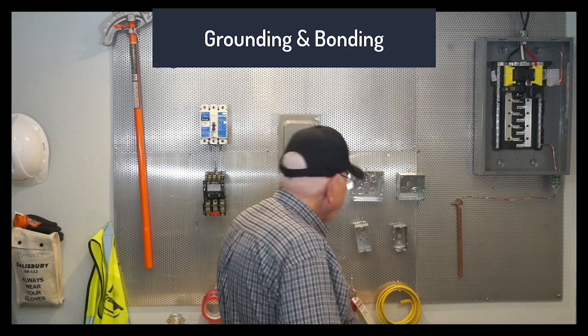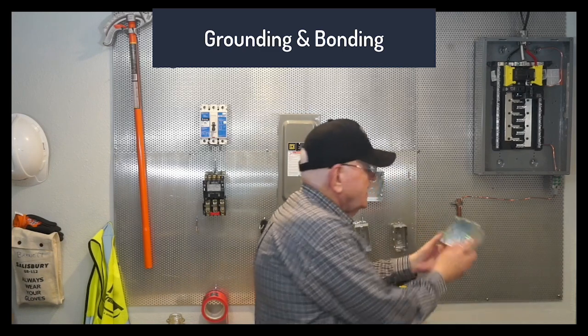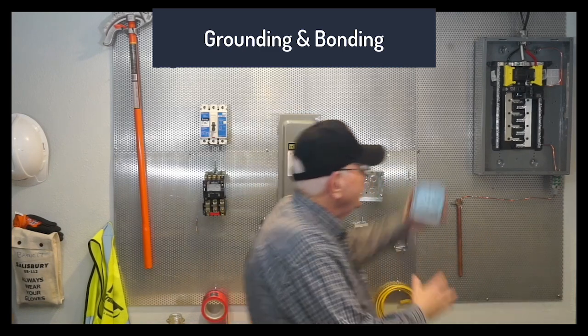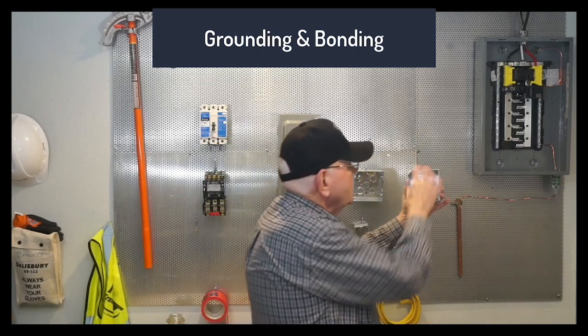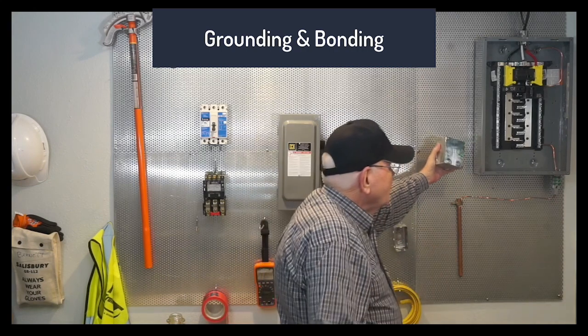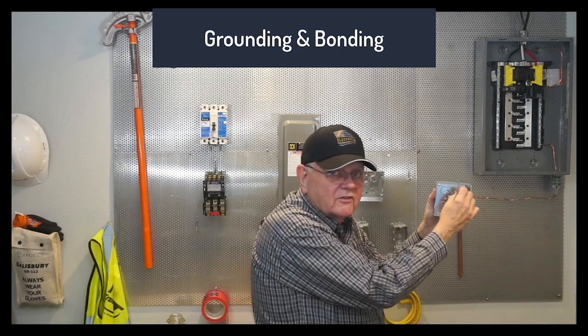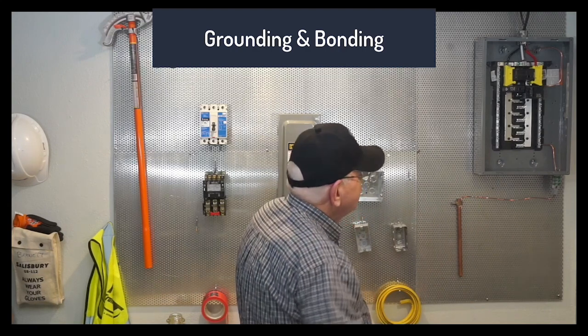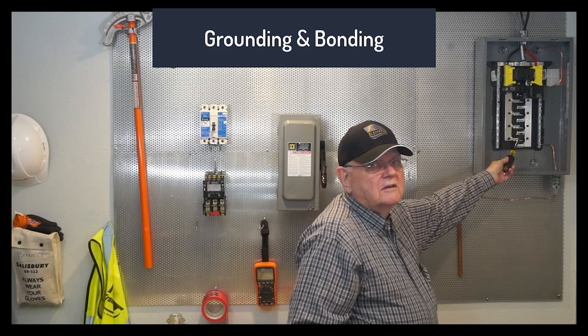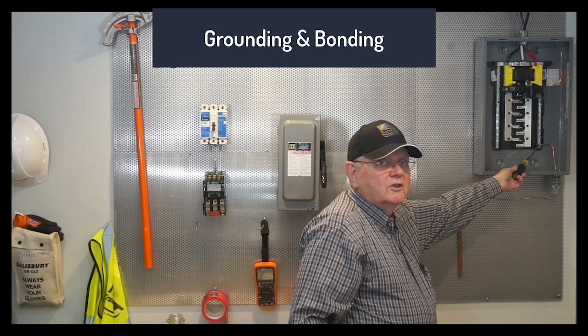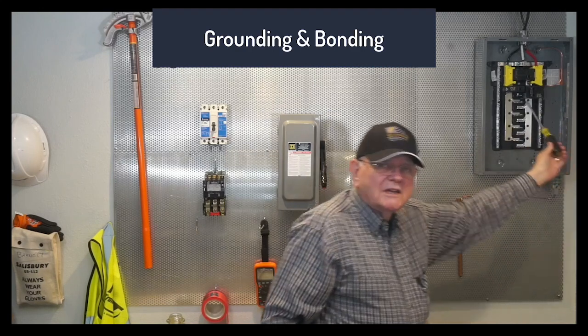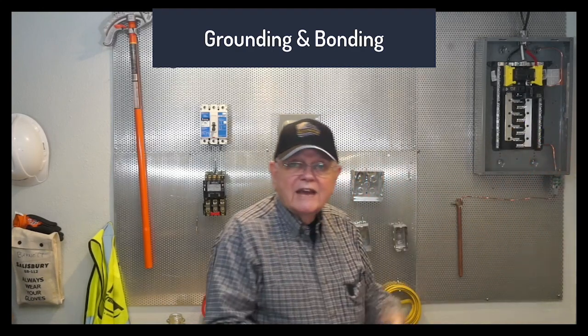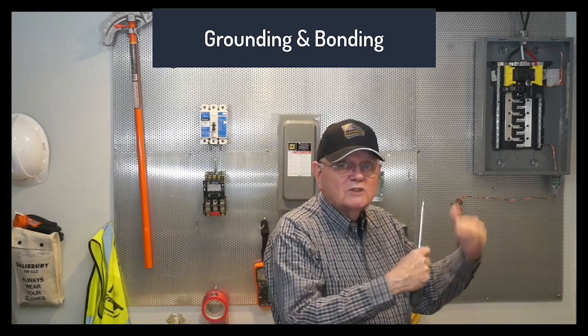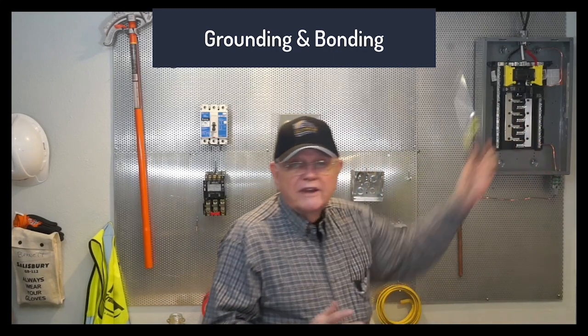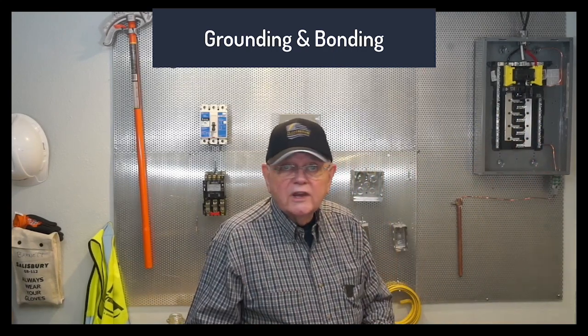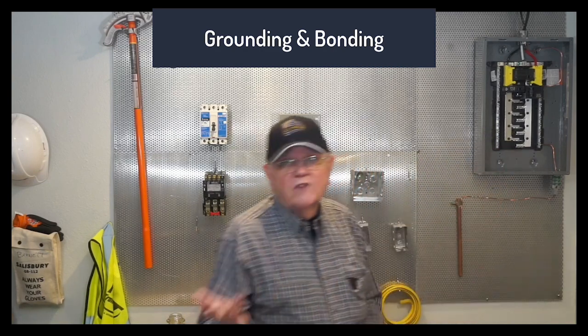So if I'm going to put some device in this box, or mount my box and connect whatever's on the inside back to my power circuit, I have to take this equipment grounding conductor and run it all the way back, and it's going to connect to the equipment grounding bus bar, which is bonded to the neutral bus bar through the green screw, which is the main bonding jumper. And that way, I'm going to carry any fault current all the way back to the source, back to the transformer, back to the neutral. And when that happens, if I've got low impedance in that circuit, the circuit breaker goes ahead and trips and clears the fault for me.